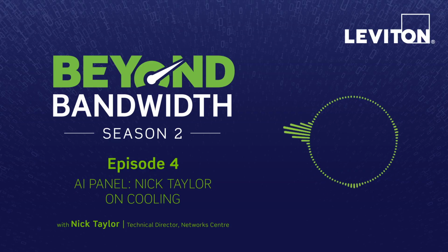Direct to chip liquid cooling. So where we're taking liquid up to the chips. So basically air can't cool them quick enough. It needs to be cooled using liquid. But also worth remembering, even with direct to chip, you still need air cooling as well, because there are other things within the servers that obviously generate heat and they still need to be cooled with air. And then immersion liquid cooling.